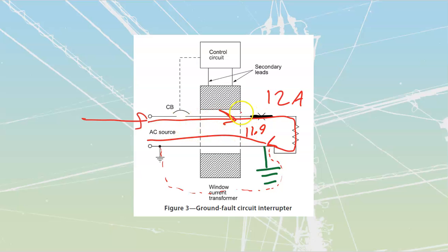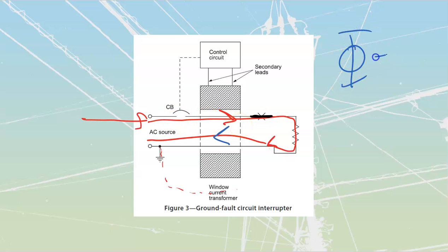All it's looking for is a net magnetic flux, which means that the amount of flux I'm going to have from current passing through here is going to be canceled out by the current that's going to pass through there, if all is good, right? If I don't have a ground fault, I have 12 amps and 12 amps, and it's only one turn, one line through there, so my ampere turns, or my phi, my magnetic flux, would be equal. Amperes times turns. A single line through counts as a single turn.